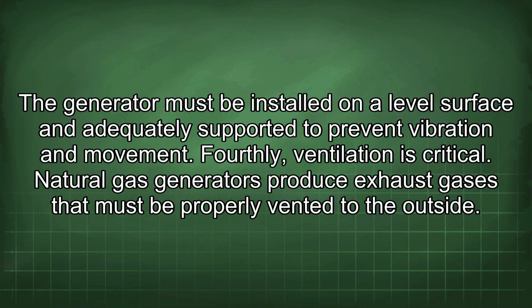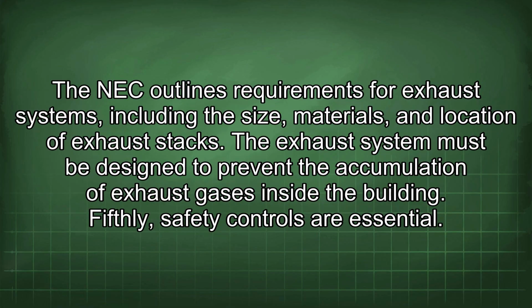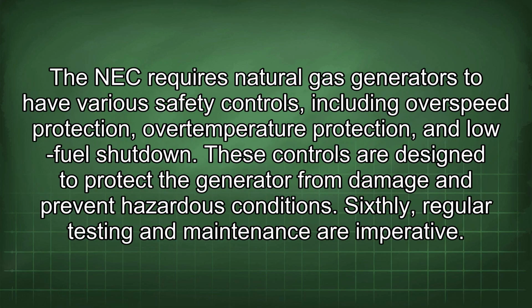Fourthly, ventilation is critical. Natural gas generators produce exhaust gases that must be properly vented to the outside. The NEC outlines requirements for exhaust systems, including the size, materials, and location of exhaust stacks. The exhaust system must be designed to prevent the accumulation of exhaust gases inside the building. Fifthly, safety controls are essential. The NEC requires natural gas generators to have various safety controls, including overspeed protection, over-temperature protection, and low fuel shutdown. These controls are designed to protect the generator from damage and prevent hazardous conditions.